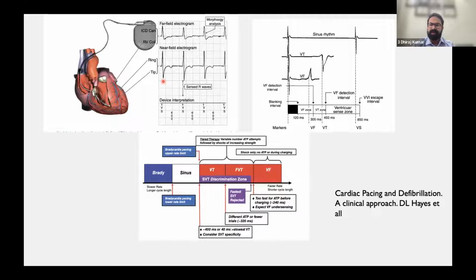And why is this important? This generally creates a bipolar-ish sort of EGM, and it is very good for timing of events and early detection of events. The far field EGM is often between the coil and the ICD can. This helps in looking at the morphological aspects. As you know, the coil and the can are far away, therefore they engulf a larger area. A larger area means a sum of depolarization vectors that you can look at. It's like a single surface lead ECG. Therefore, a far field EGM is important for looking at the morphology.